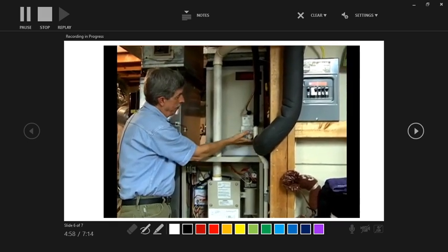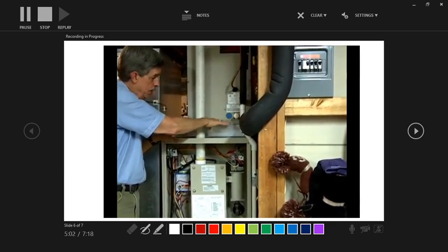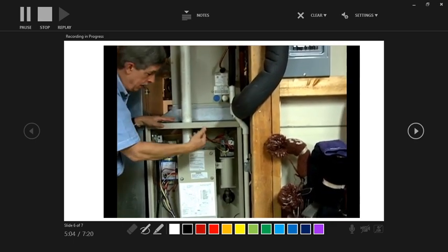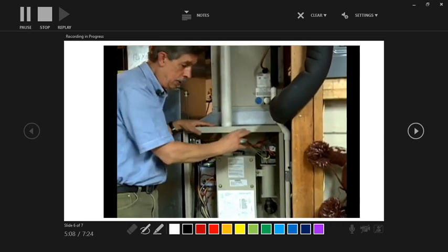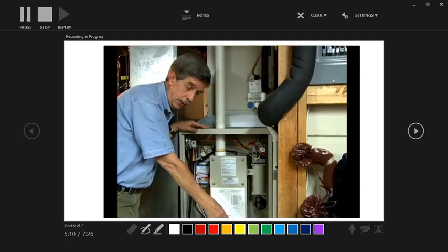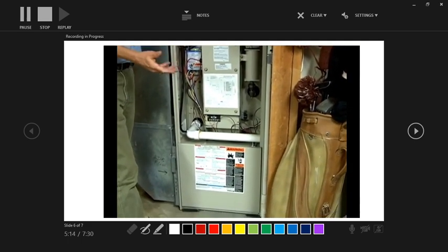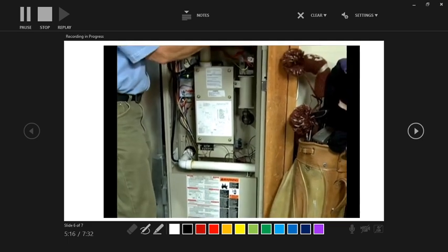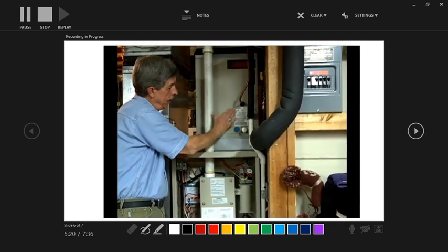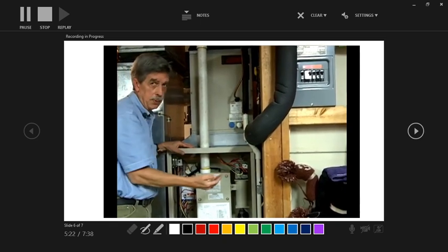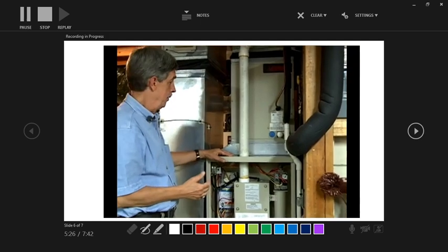Now, we also have here a drain. We'll make sure this drain is kept clear, so it's not spilling water over here and down the sides of the furnace, inside the furnace, where it can cause great damage. So you want to see where your condensate line comes into the home, where it's draining. Make sure it's draining freely. If it's backed up, well, then algae loves to grow in here, and it'll block it up like a little dam in there. A lot of times you have to cut this and go through some different construction to take care of this. So again, you might want to call a company to deal with this.